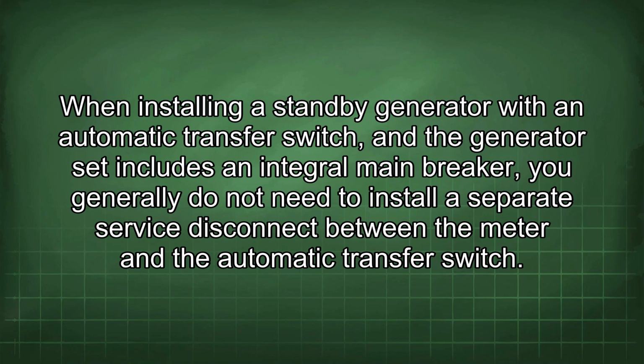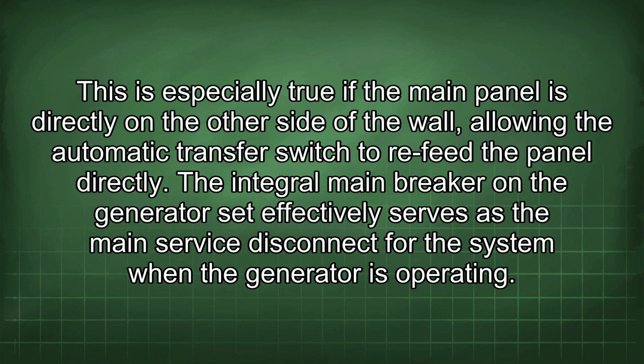When installing a standby generator with an automatic transfer switch, and the generator set includes an integral main breaker, you generally do not need to install a separate service disconnect between the meter and the automatic transfer switch. This is especially true if the main panel is directly on the other side of the wall, allowing the automatic transfer switch to refeed the panel directly.